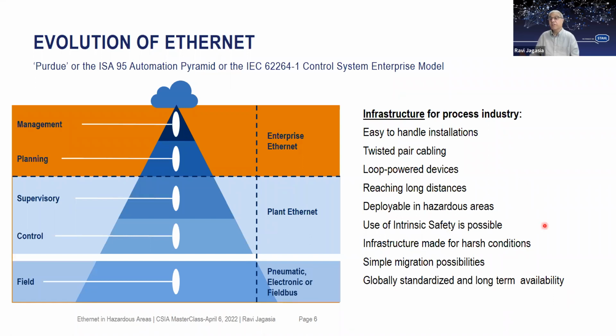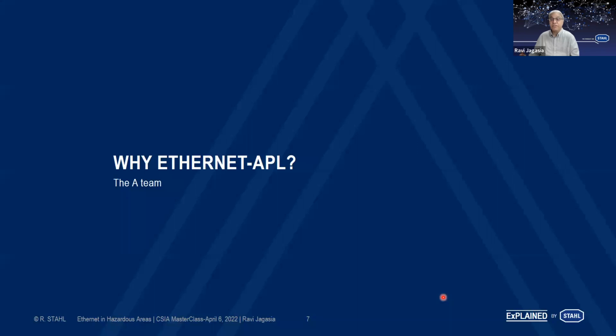You definitely need to do maintenance. In that case, intrinsic safety is a big help because that allows for live maintenance. You wanted to ensure that you had migration possibilities from a smaller system to a larger system. And then of course, you wanted a standardized solution which was uniform across the world, and not one where what you get here in the US could not be used in Europe or Asia Pacific, or the other way around. So that being the requirement was the formation of Ethernet-APL. We need to work together to evolve a solution which will be global.